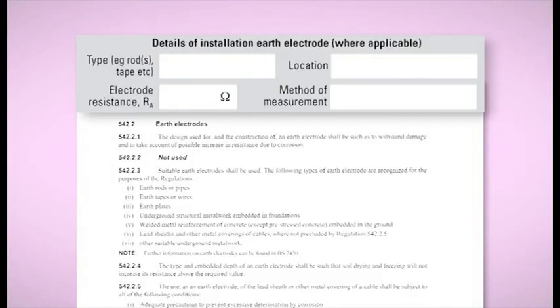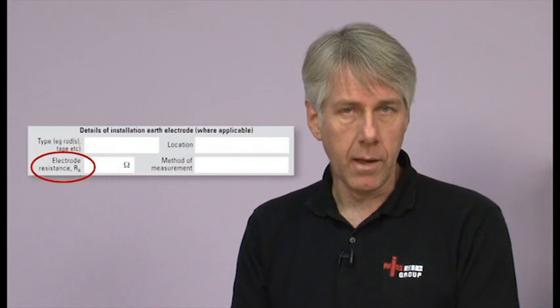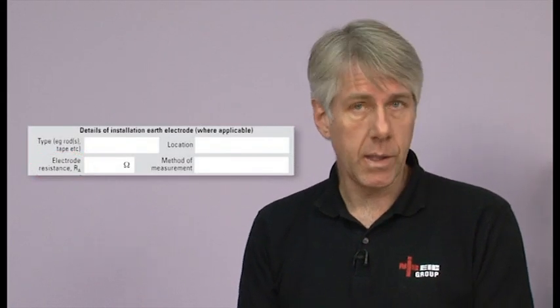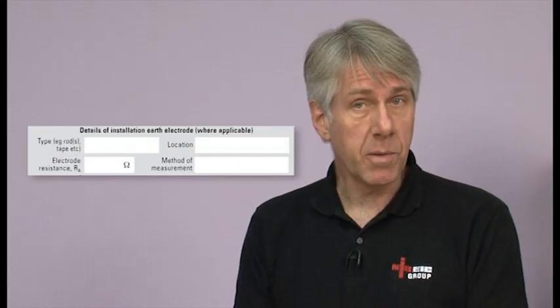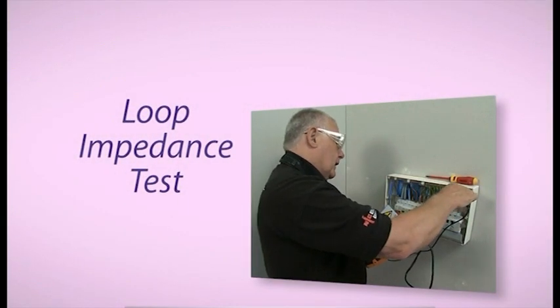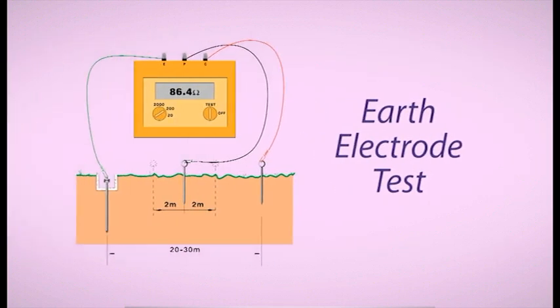The acceptable types of earth electrode are listed in Regulation 542.2.3. It will also be necessary to measure and record the electrode resistance RA, and you must also write down how this was measured, because there are several test methods that can be used. For example, where there's a supply, a loop impedance tester may be used, or where there's no supply, by using an instrument and proprietary earth electrodes to undertake the fall of potential method.